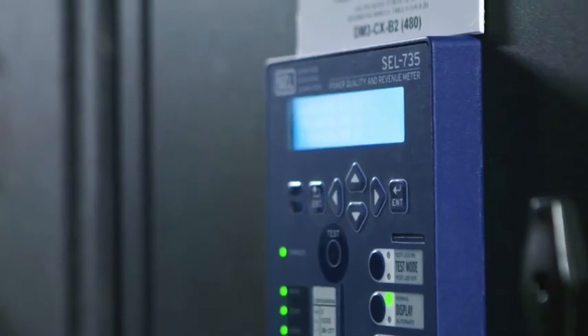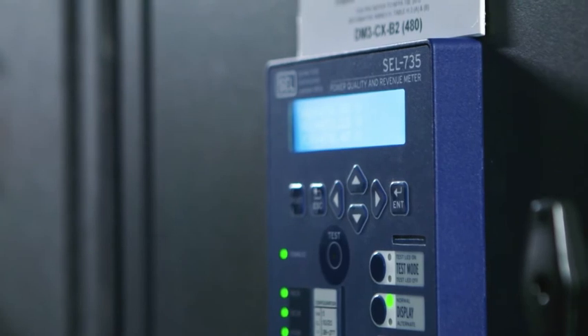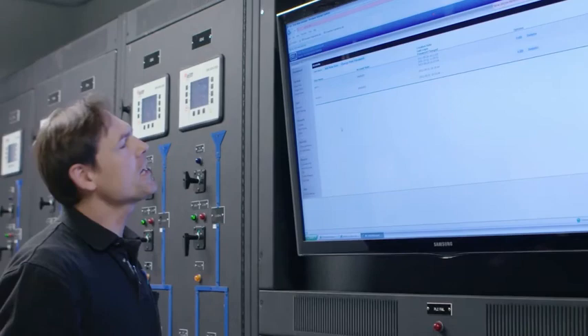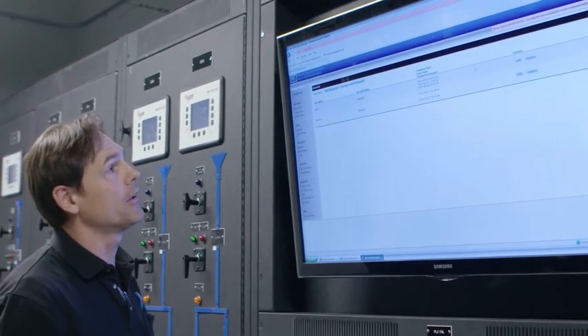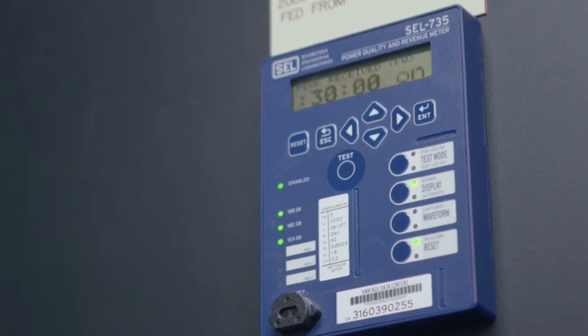What we started to integrate with the 735 series meter is waveform capture. So if we have a breaker trip event, it will trigger a waveform capture, and we're able to go back later and see exactly what caused that trip event.